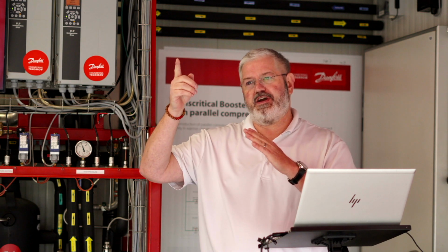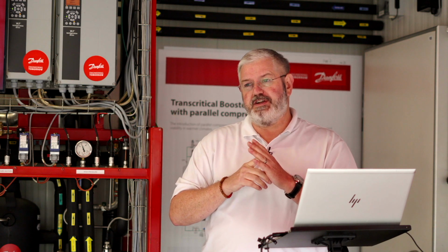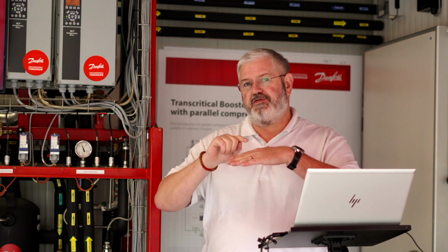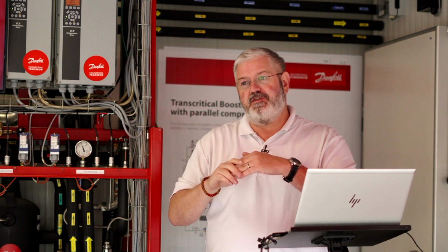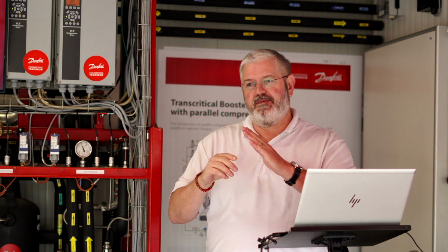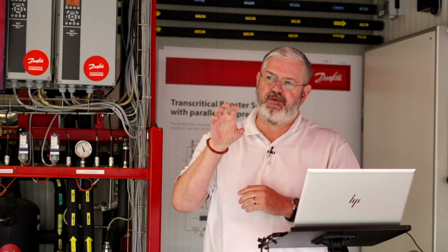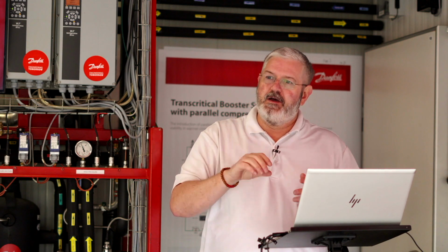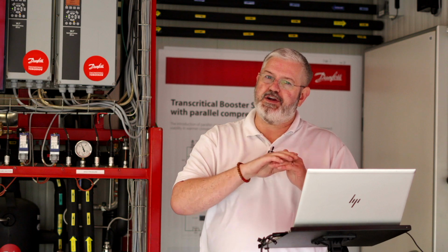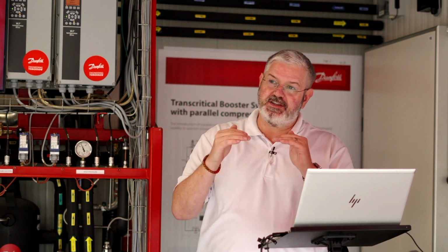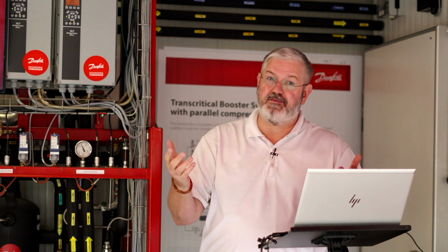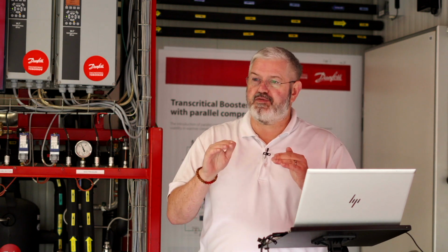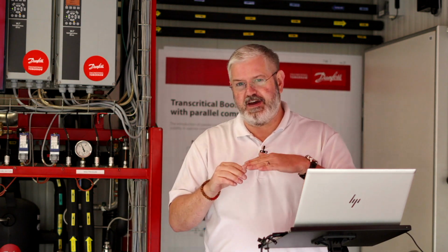I want to turn on parallel compression. The way you turn on parallel compression is simply closing the receiver valve, which forces the load to go that way. So if you think about it, the receiver valve is normally open, and the parallel compression set point is set to flash tank pressure. So there's no reason for any pressure to make its way to the suction side of the parallel compressors to make them turn on. So we cause that pressure to rise by closing the receiver valve, which forces pressure to build, which will turn on your parallel compressors. And you get to set that how you want, when you want it to turn on, within the software.